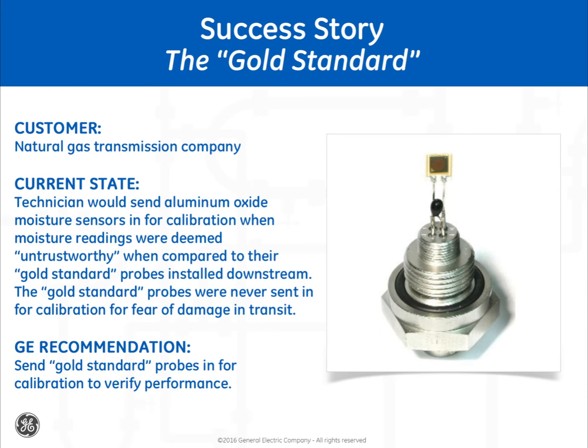To minimize the possibility of damage or loss in transit, the technician did not send back these standard sensors. Increasingly, he found that the recalibrated sensors would read wetter than expected and reported what he felt were false positive readings. At the same time, the standard sensors would hold constant at a significantly drier moisture reading. To help resolve the discrepancy in readings and the ensuing differing opinions between the maintenance and operations teams on the reasons for the discrepancy, we were able to convince this customer to send in their gold standard sensor for calibration.